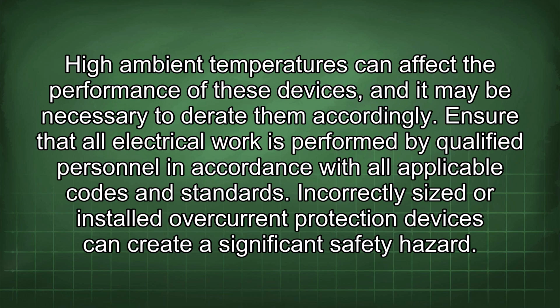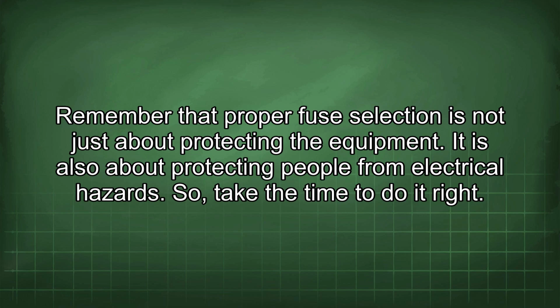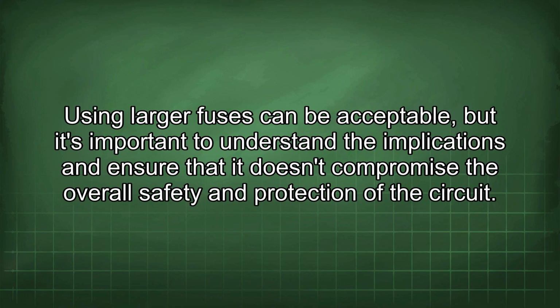Ensure that all electrical work is performed by qualified personnel in accordance with all applicable codes and standards. Incorrectly sized or installed overcurrent protection devices can create a significant safety hazard. Remember that proper fuse selection is not just about protecting the equipment. It is also about protecting people from electrical hazards. So take the time to do it right. Using larger fuses can be acceptable, but it's important to understand the implications and ensure that it doesn't compromise the overall safety and protection of the circuit.